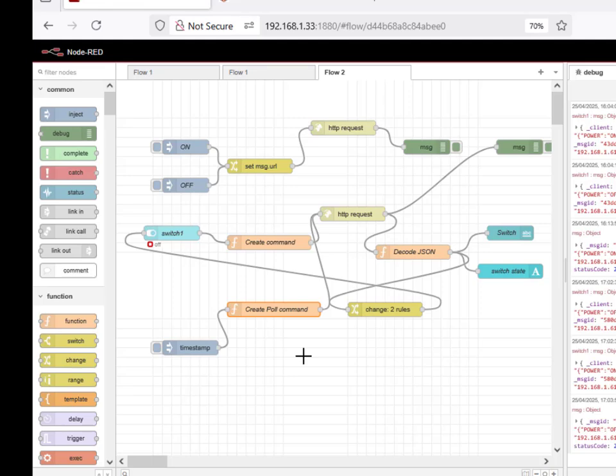And so then you have to decide at what interval do you want to read it. Do you want to read it every minute, every 10 seconds? Obviously the more often you read it, the more network traffic you're going to generate. Over a local area network it probably doesn't make that much difference, but over a wide area network it will do.